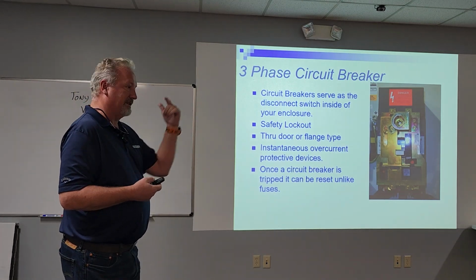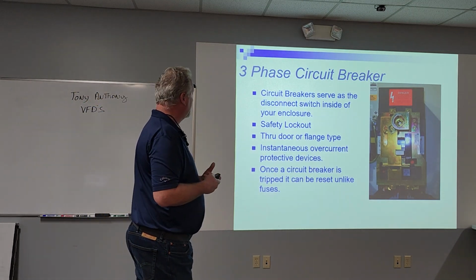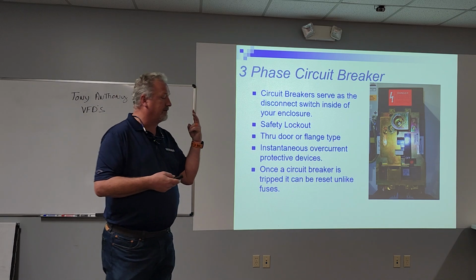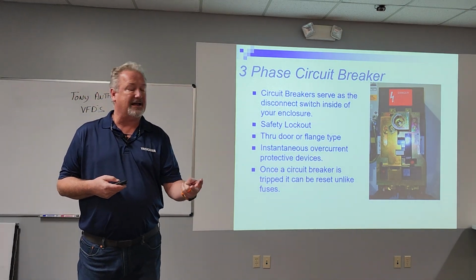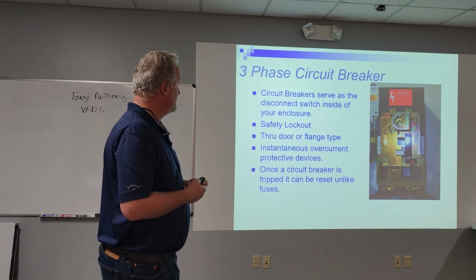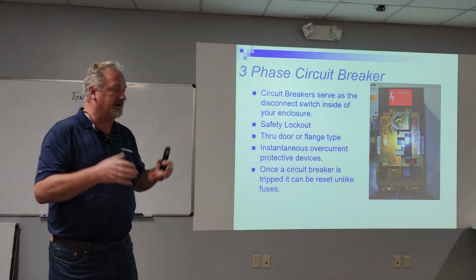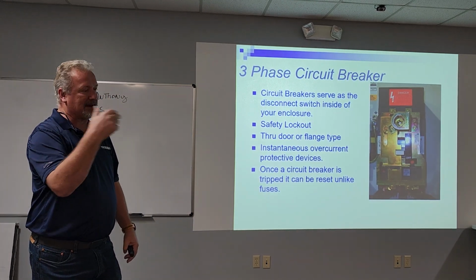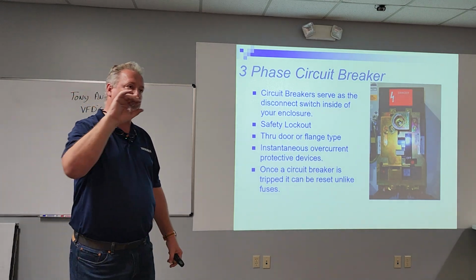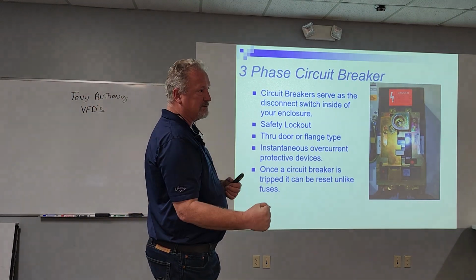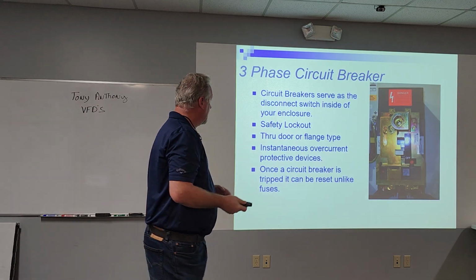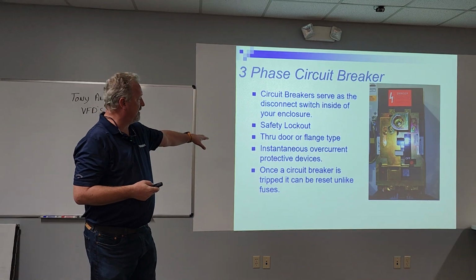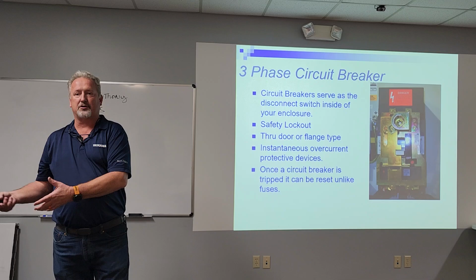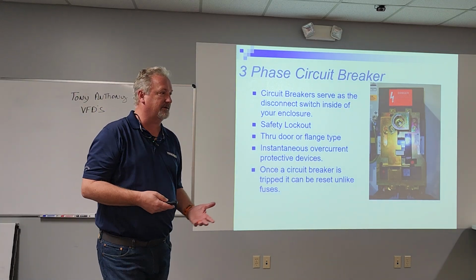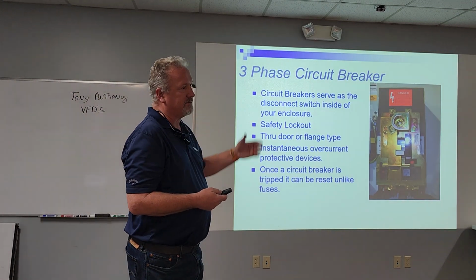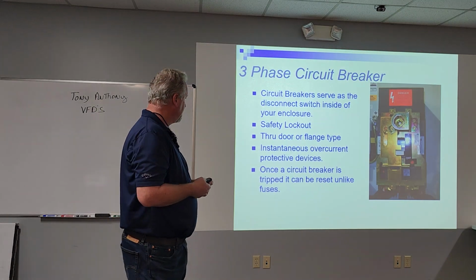Circuit breakers serve as the disconnecting means to disconnect power from the drive. They help us for safety for lockout, tagout procedures. If you see a drive in a panel, we can have different types of handles to operate that breaker. They can be through the door, or they can be a flange style, which is a pull down style you've probably seen. They provide instantaneous overcurrent protection. So if there's a short circuit, it's going to protect the drive from a short circuit, or protect other equipment from the short circuit if the drive short circuits.